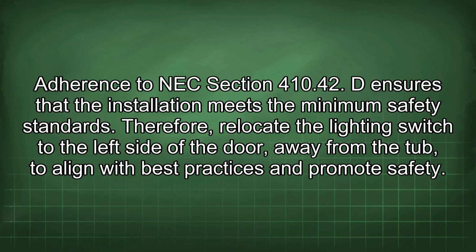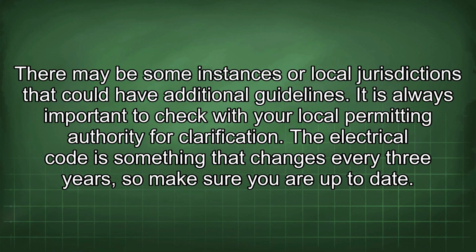Therefore, relocate the lighting switch to the left side of the door, away from the tub, to align with best practices and promote safety. There may be some instances or local jurisdictions that could have additional guidelines. It is always important to check with your local permitting authority for clarification. The electrical code changes every 3 years, so make sure you are up to date.